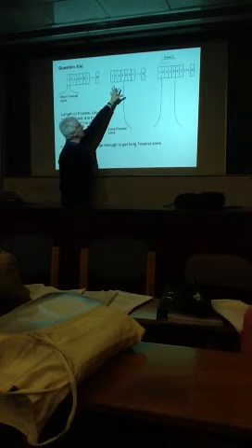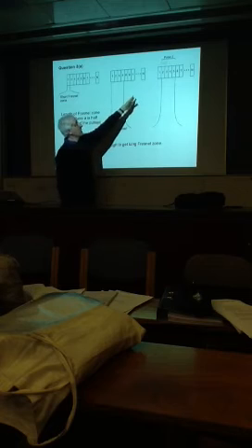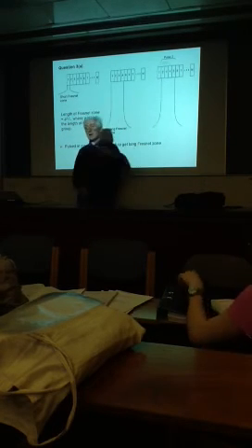And so the first line is sampled by pulsing groups 1 to, let's say, 4. The next line is sampled by pulsing 2, 3, 4, 5. The next one will be 3, 4, 5, 6, and so on. And so you advance the group one transducer at a time. So the number of lines is still pretty much equal to the number of transducers, yet we have enough within the group to get a nice long Fresnel zone.